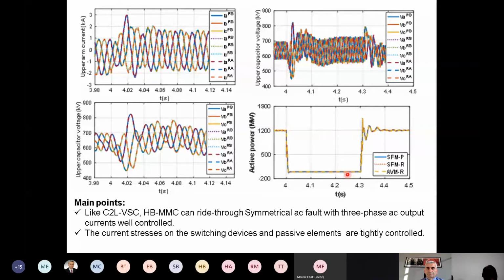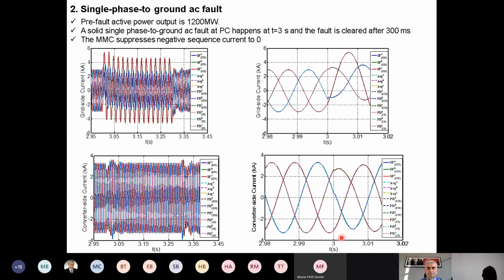So the main point here is that, like a conventional two-level converter, the half-bridge MMC can ride through a symmetrical AC fault with three-phase AC output currents well controlled and restrained. So the current stress in switching devices and passive elements is tightly controlled. For a single phase fault, here in the negative sequence current controller, we suppress the negative sequence current to zero, so as to maintain the current at the converter side balanced.